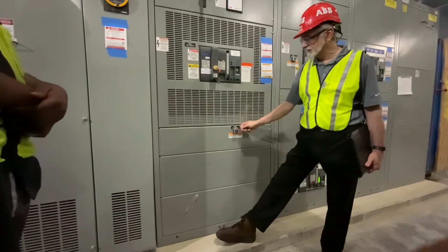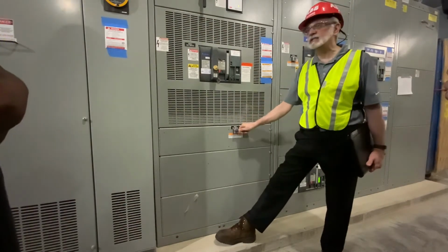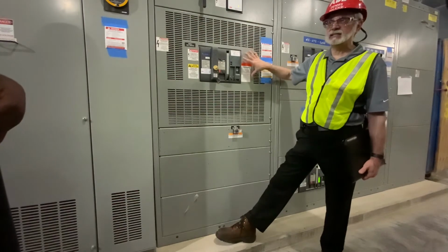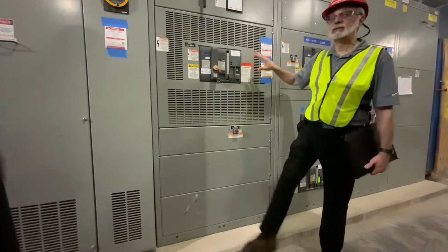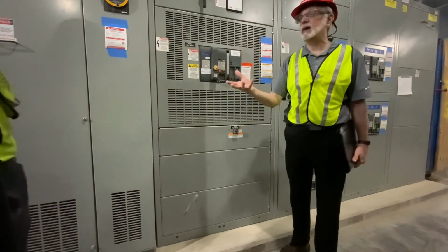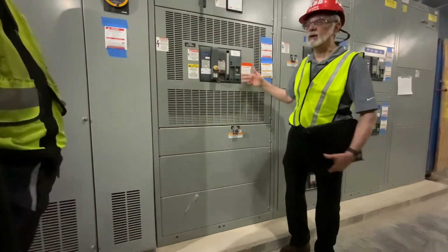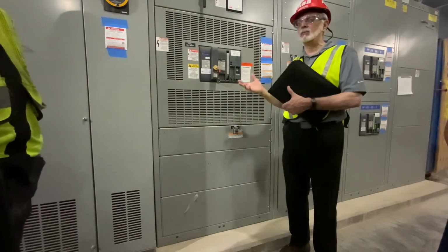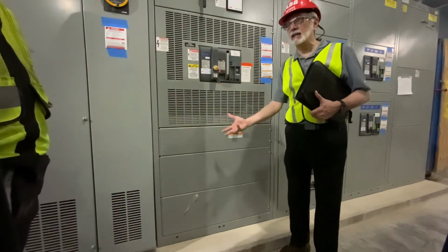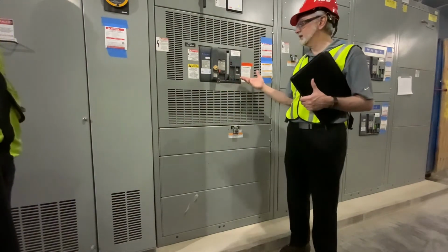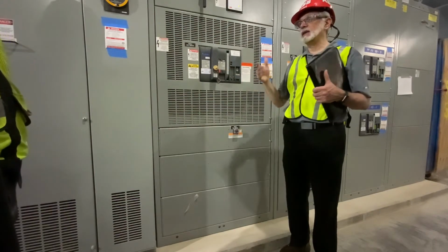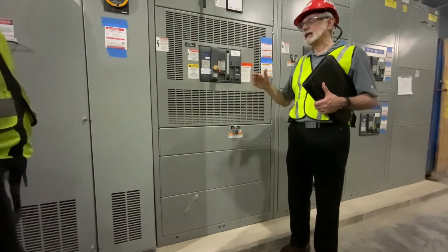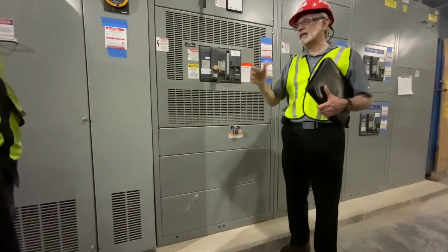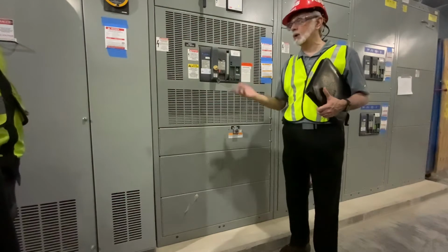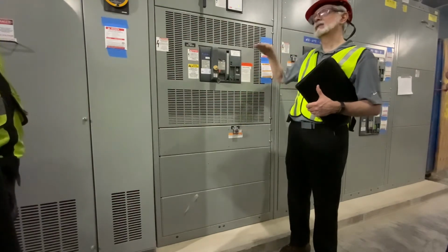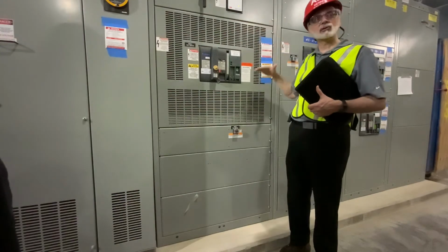What happens here is you have the ability, by activating this switch, to change the instantaneous performance of this breaker. So instead of this breaker being at like 10x, this is a 2000 amp breaker on an instantaneous function, it would normally be set to trip at 20,000 amps. 10 times 2,000 would be 20,000. Well, one of the things that you can do to mitigate arc flash is to put in a lower set of values, typically somewhere around 1 or 1.5. So that way, instead of having to wait to 20,000 to trip, the breaker trips at 3,000.